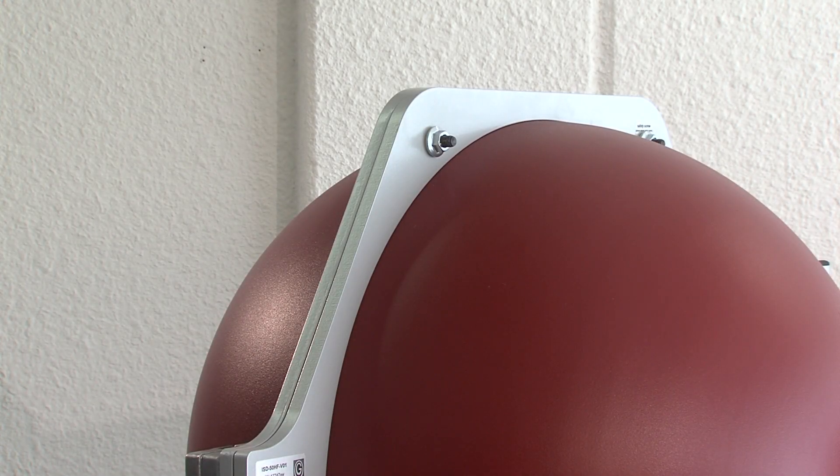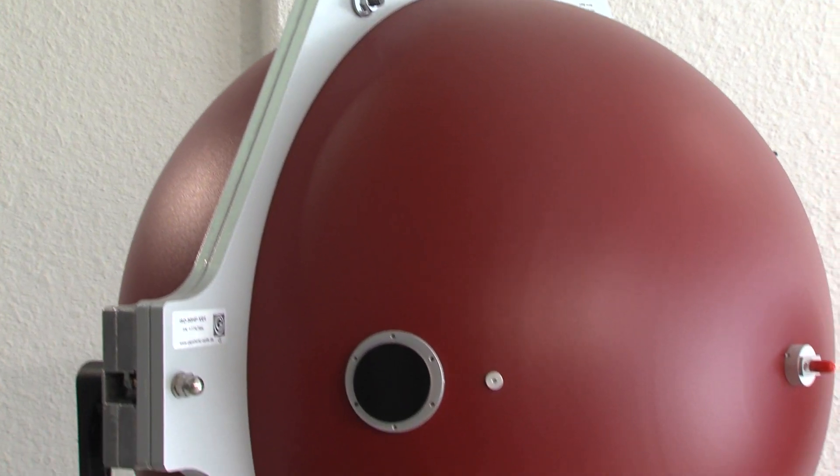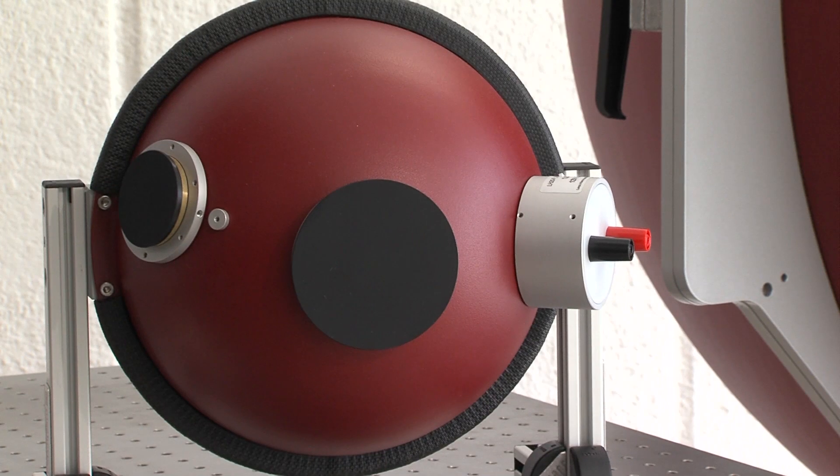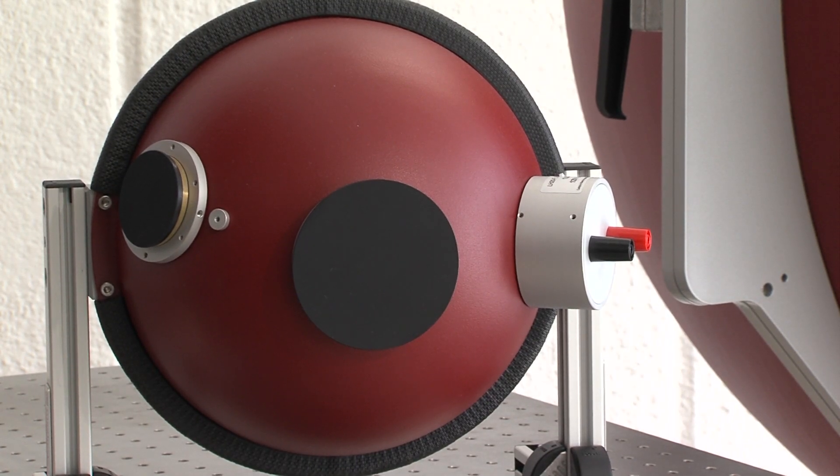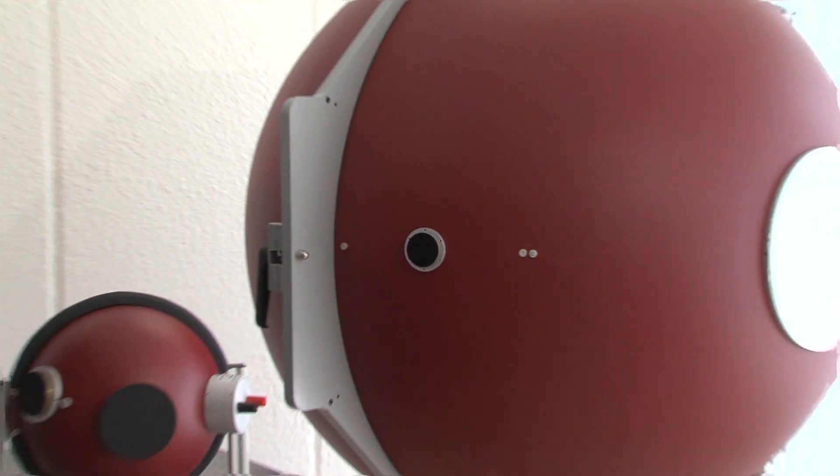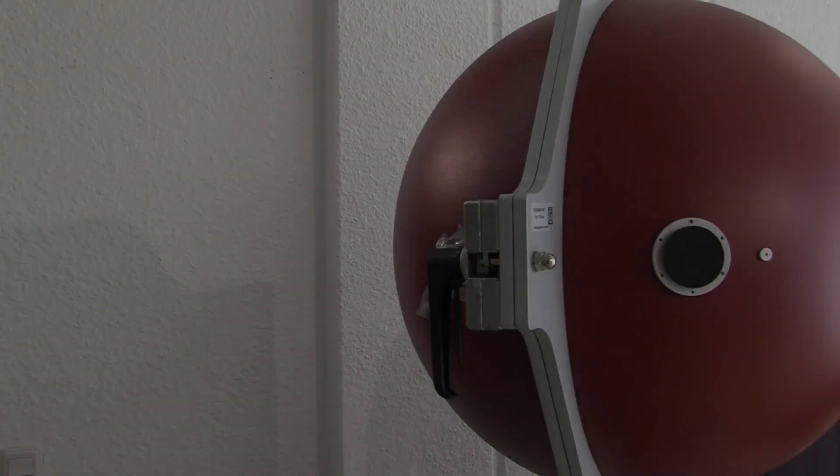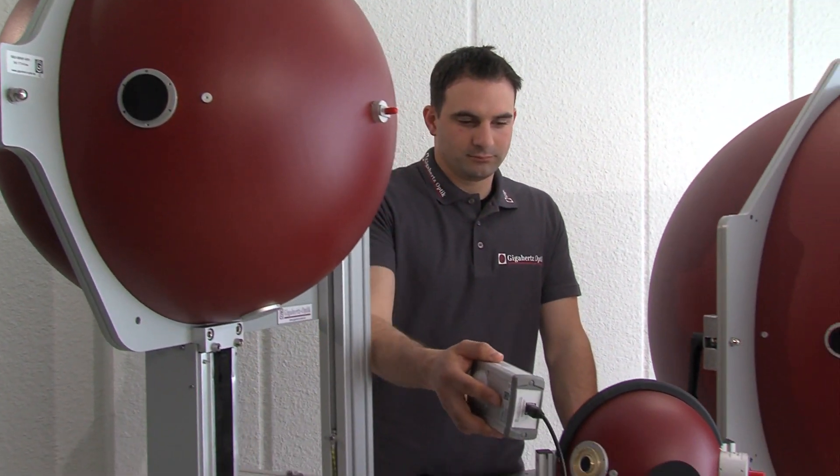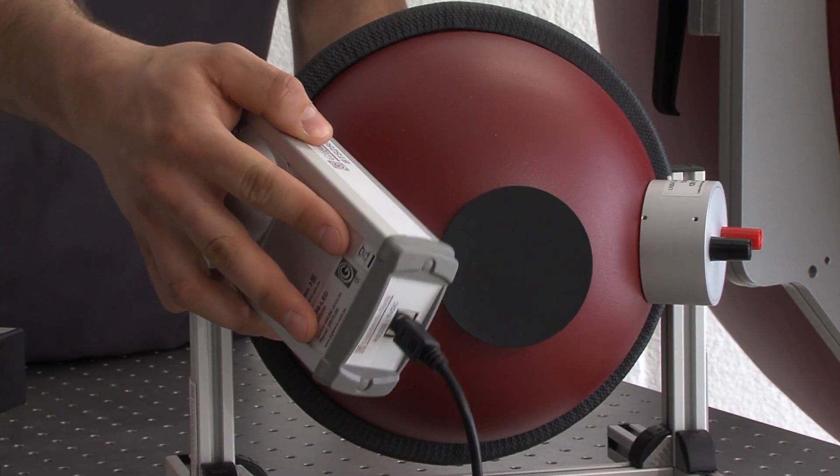To measure luminous flux of larger size LED lamps and fixtures, the LED Tester can be combined with large diameter integrating spheres. Gigahertz Optik makes integrating spheres for the LED Tester from 21 to 100 centimeters in diameter. The mating bayonet type mount on the integrating sphere makes attaching the LED Tester simple and secure.